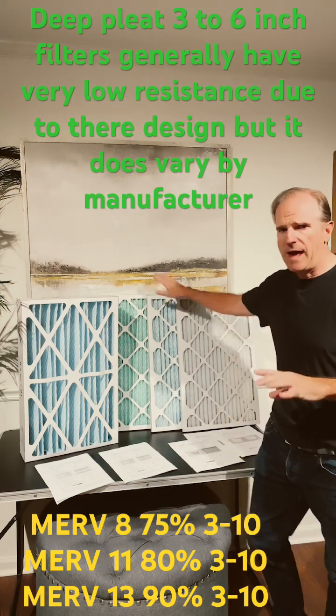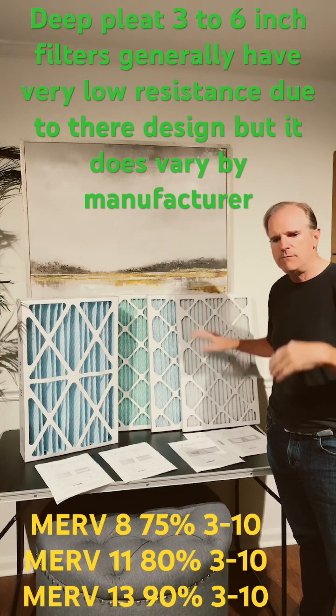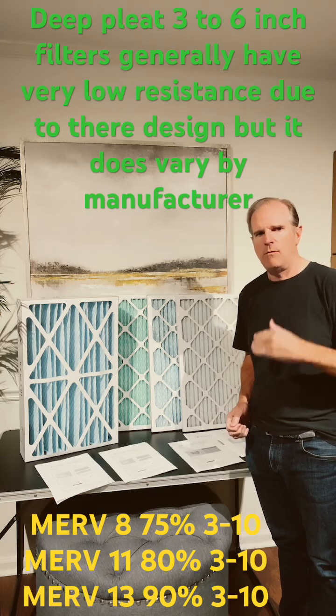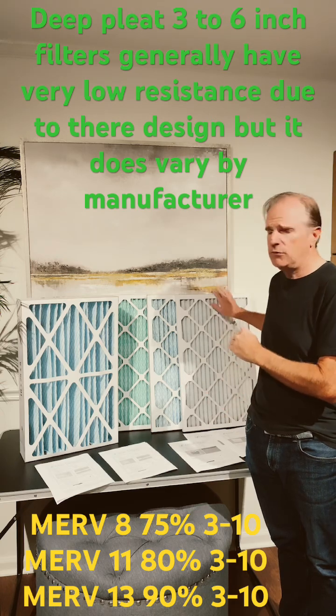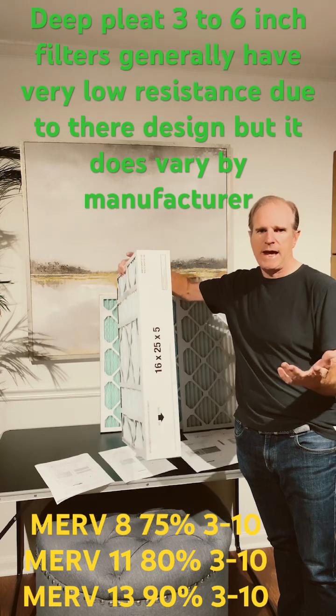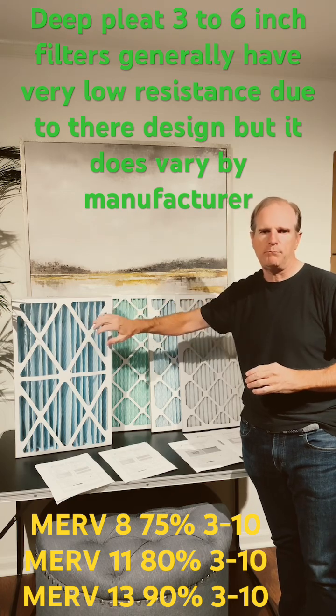At 85%, the resistance is going to go up on one-inch filters. Generally, newer systems can handle that resistance from MERV 8 to MERV 13. Older systems may struggle with the airflow and may need to go with the lower level like a MERV 8. But as you go to a larger filter, you can generally handle a much greater MERV because the resistance is much lower due to the deeper pleats.